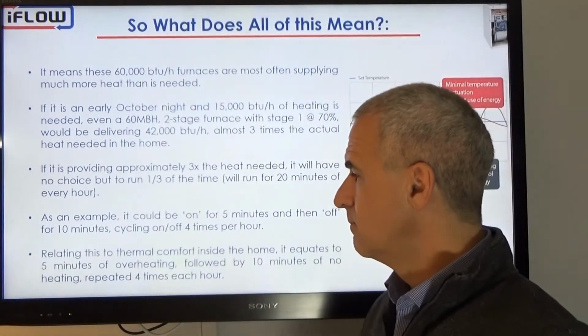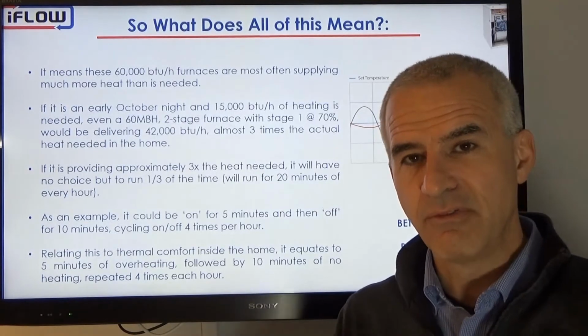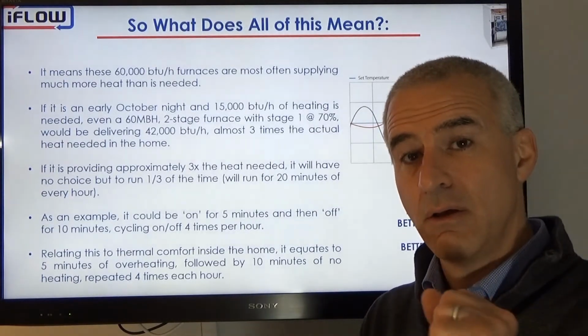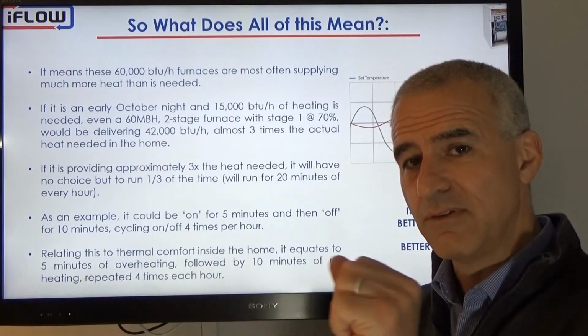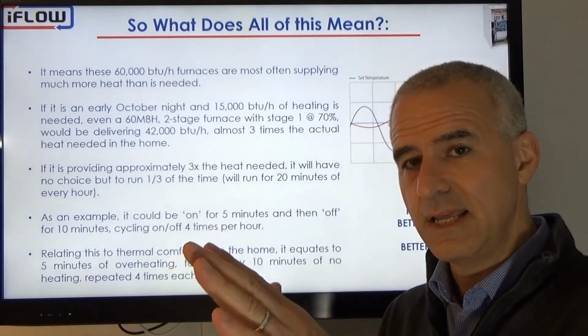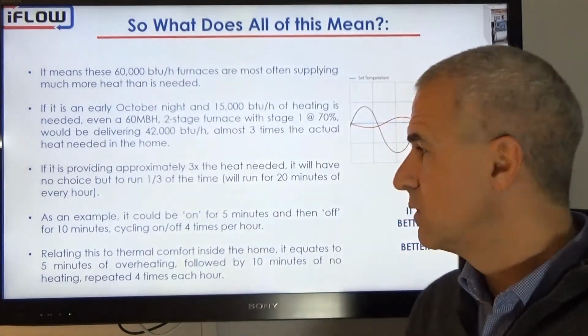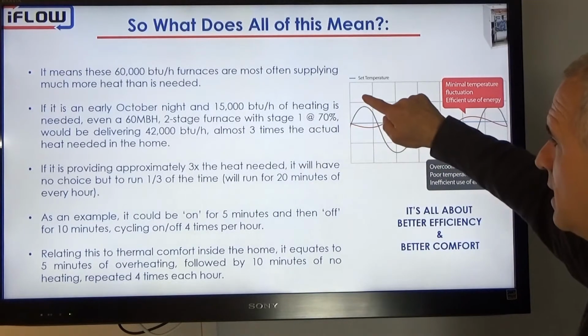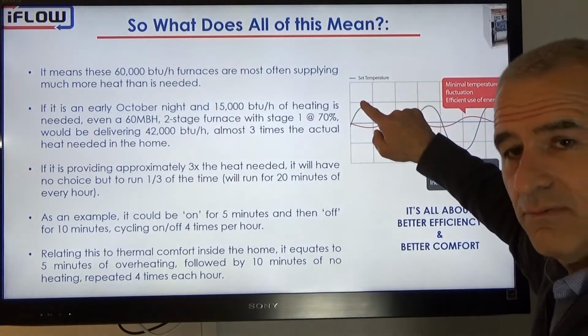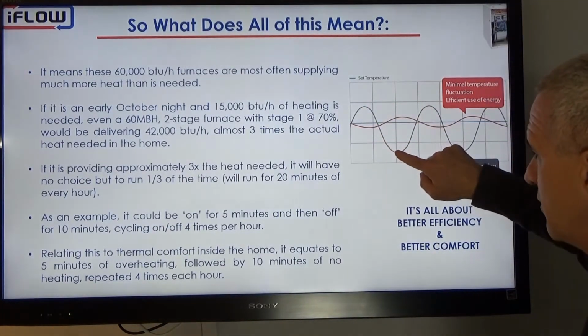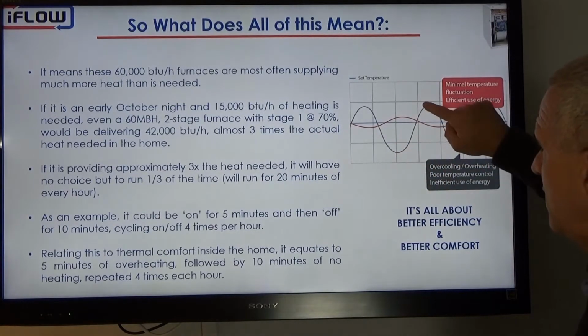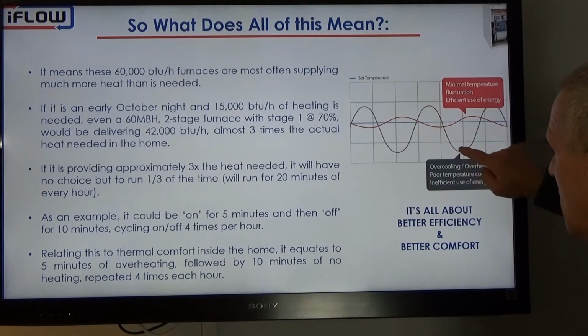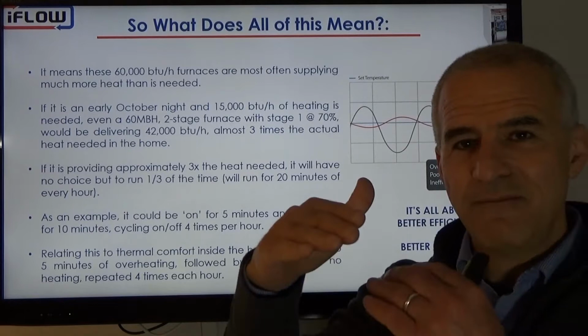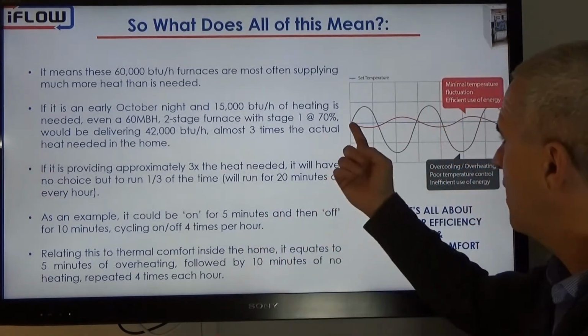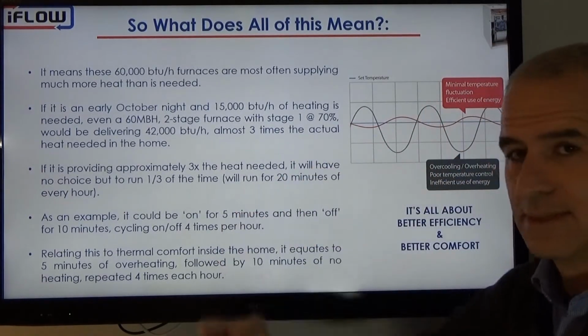Now what does that mean? Well, I'm coming on for 5 minutes, delivering 42,000 BTUs worth of heat for that 5 minutes, so more heat than I need, and then I'm off for 10. So the temperature is going to go up quickly, and then the furnace is going to go off, and then it's going to drop gradually over that 10 minutes, and then it's going to come on again and heat up 5 minutes quickly, and then down. It means there's a significant variance or stratification from the set point.